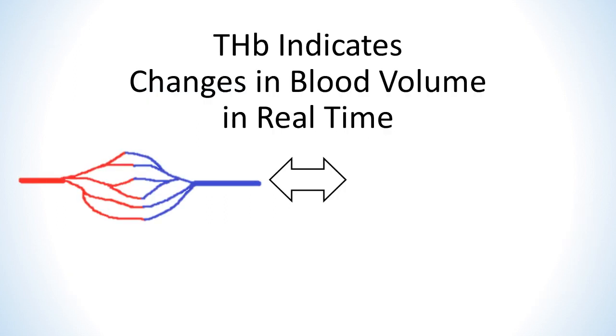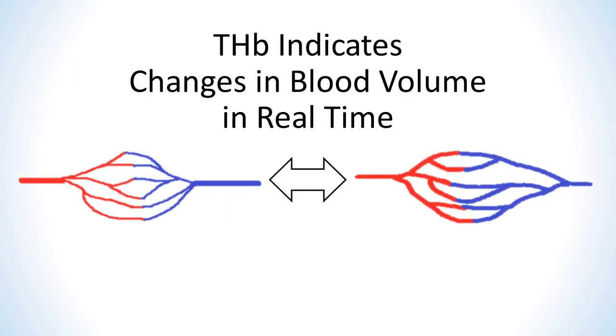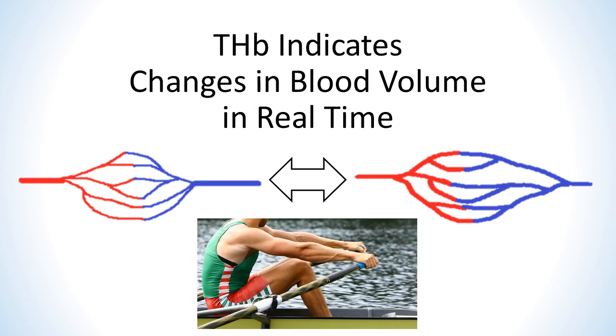The primary use for the THB metric is to indicate changes in blood volume. It can't measure blood volume in any absolute sense because many factors are not known absolutely, but it is useful to tell if blood volume is simply going up, down, or staying the same. If you move the sensor to a different position with a different fat layer thickness, the magnitude of the THB reading will differ. However, once the sensor is fixed, any changes in THB reading can be assumed to reflect changes in blood volume.